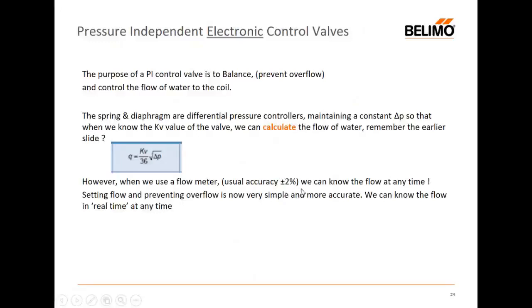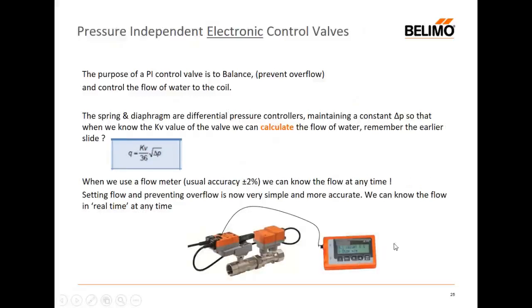These can be very accurate, some manufacturers as good as plus minus 2%. And usually you can access that flow rate at any time by directly reading the flow from the actuator using a small handheld. This is a similar sort of device that I'm talking about, where we put an RJ45 cable into an actuator and we get a direct flow reading at any time that we wish. That's simply not possible with mechanical valves, but with electronic, it is. The information is very, very accurate indeed.